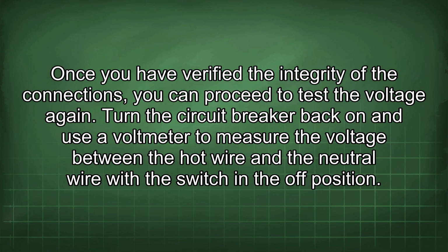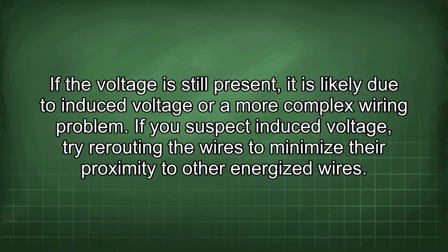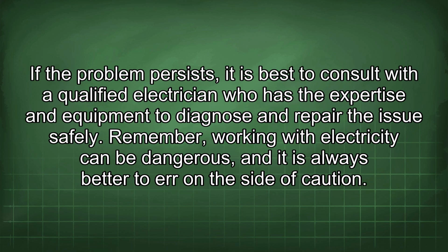Turn the circuit breaker back on and use a voltmeter to measure the voltage between the hot wire and the neutral wire with the switch in the off position. If the voltage is still present, it is likely due to induced voltage or a more complex wiring problem. If you suspect induced voltage, try rerouting the wires to minimize their proximity to other energized wires. If the problem persists, it is best to consult with a qualified electrician who has the expertise and equipment to diagnose and repair the issue safely.